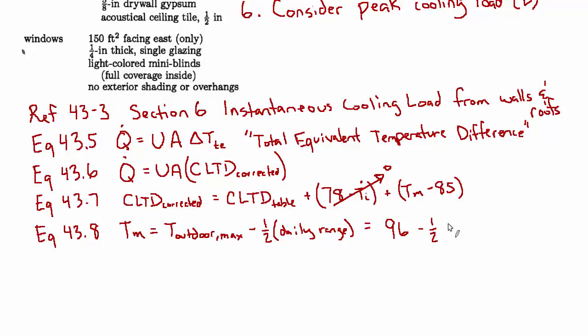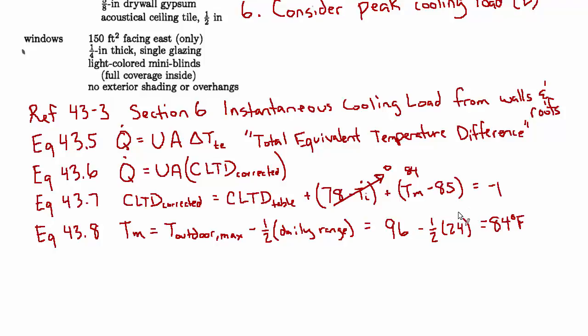The outdoor design temperature is 96°F and we subtract half the daily range of 24, so we subtract 12, giving a mean temperature of 84°F. Plugging that in, the correction becomes 84 minus 85, which is minus one. So the correction would be to take the table value and subtract one. For simplicity in this problem, I'm not doing the table lookup, so I won't show that correction — I'll take the cooling load temperature difference values from the answer solution and apply them directly.